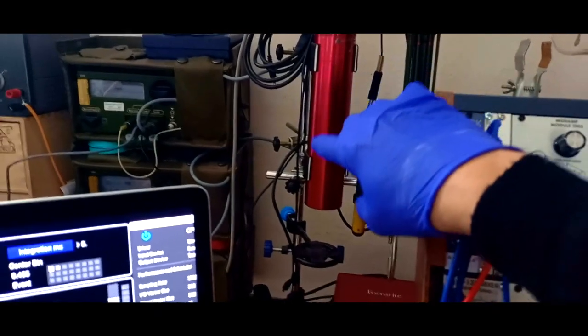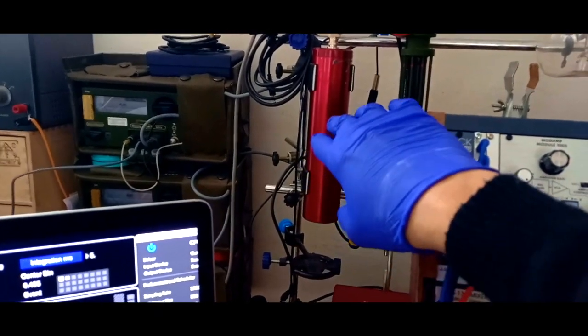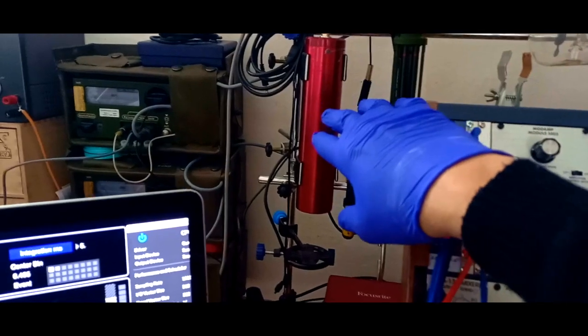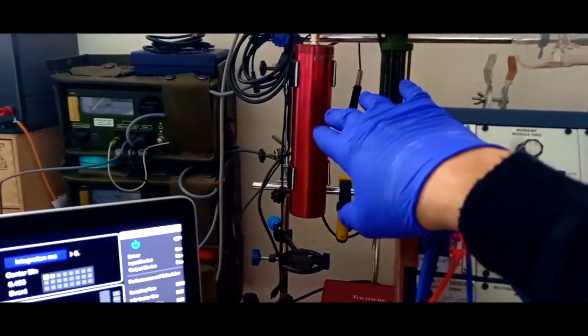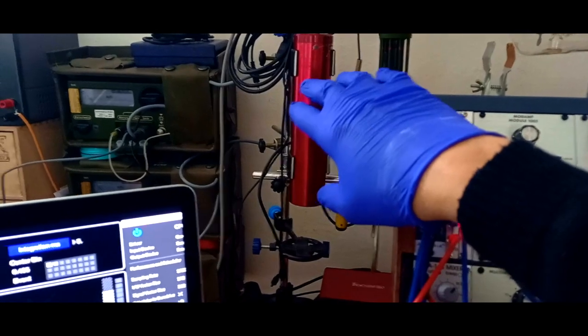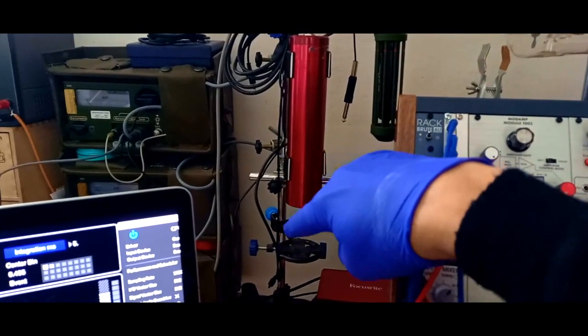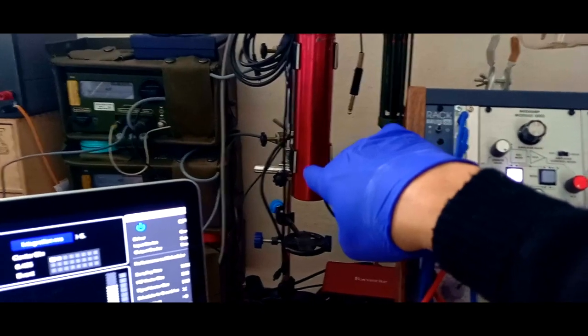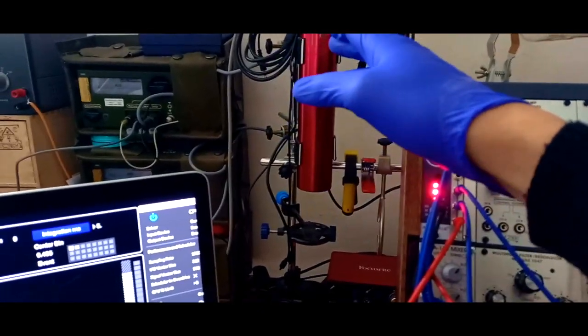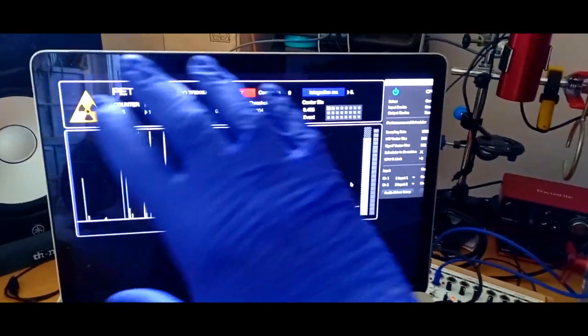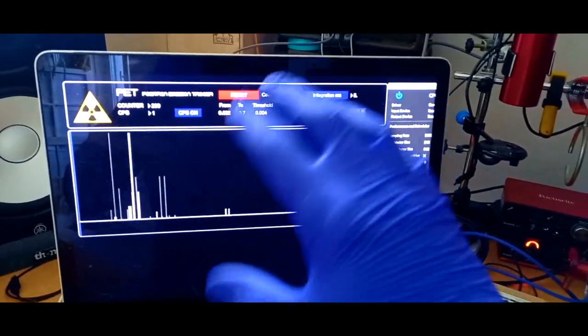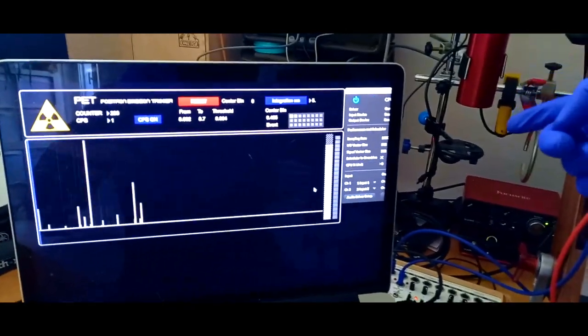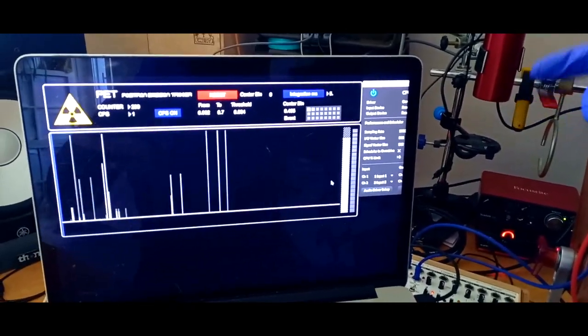This scintillator, which is a special form of radiation detector, not only can count particles but can calculate the energy of every gamma ray that hits the counter. Therefore it's used with spectroscopes to give us a spectrum of the energies, and therefore we can infer the kind of isotope we are analyzing.